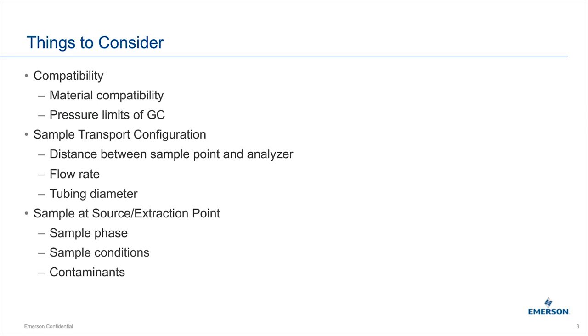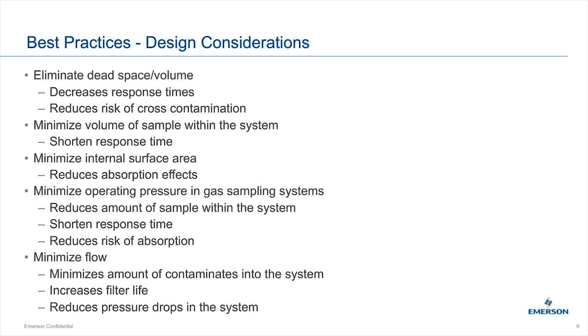Some best practices: first, eliminate dead space and volume. More volume means longer response time for your sample to reach the GC. Dead spaces can also trap liquid or gas that causes contamination when you switch samples, because you have to purge out the old gas. Best practice is to eliminate dead spaces as much as possible.